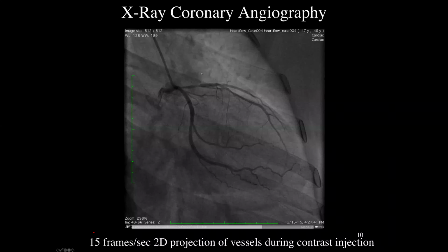And you have to have the time resolution because this thing's moving. So if it took 200 milliseconds to take this picture, the vessel would have moved a considerable distance and it would all get blurred out. So you need a flash. So there's temporal resolution, spatial resolution, and signal to noise in order to achieve your goal. And depending on what your goal is, those parameters change.